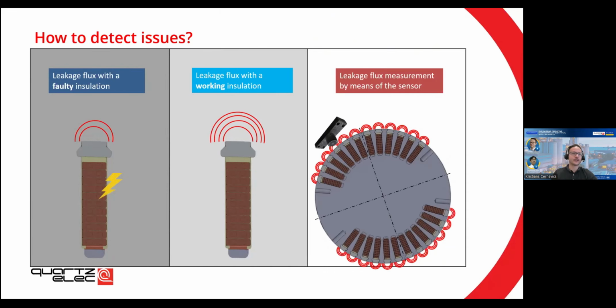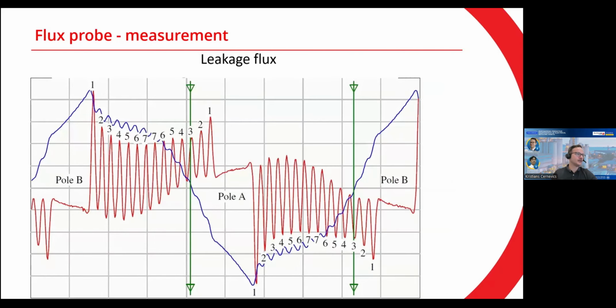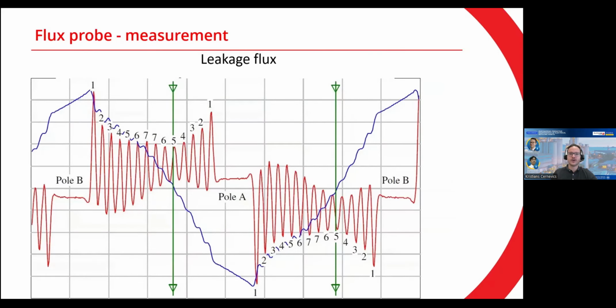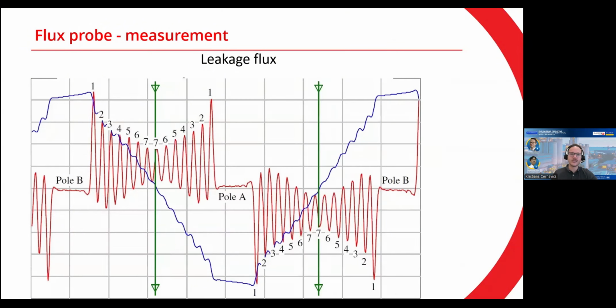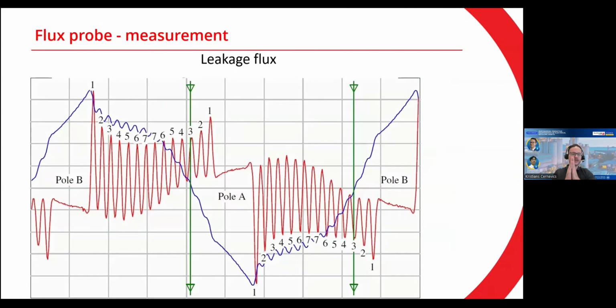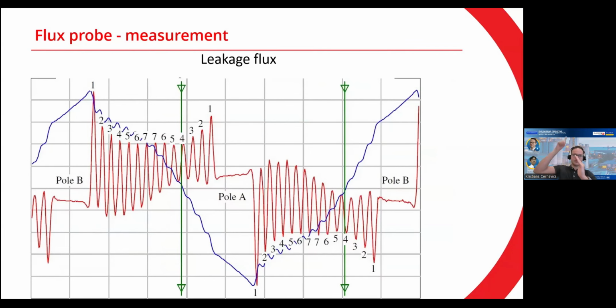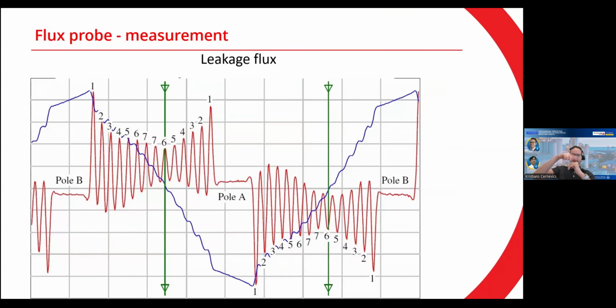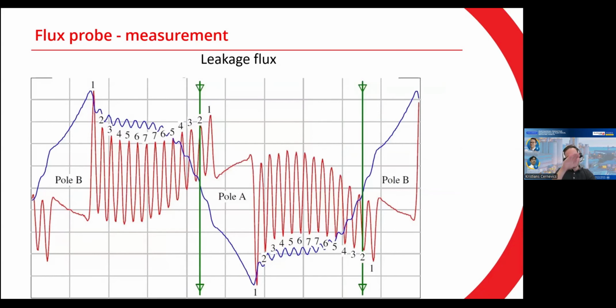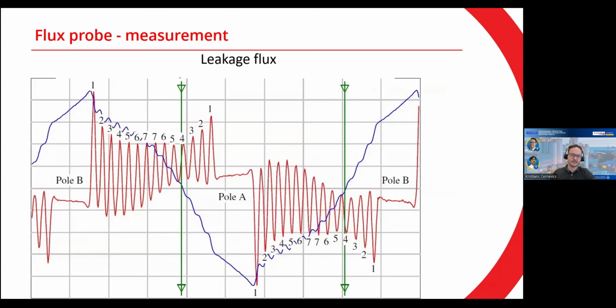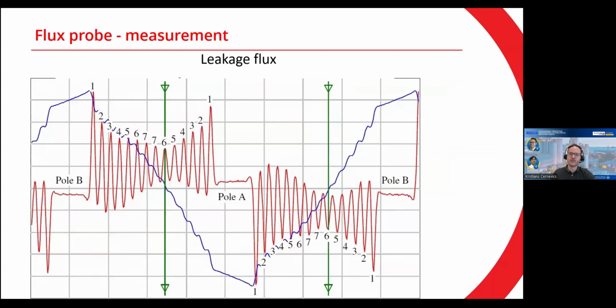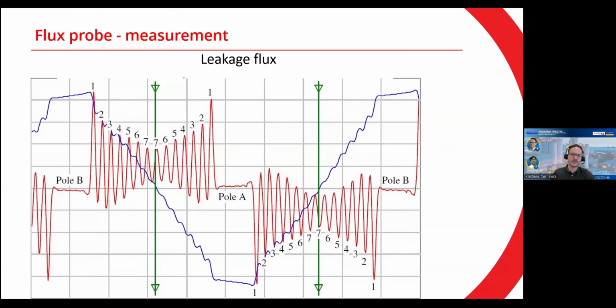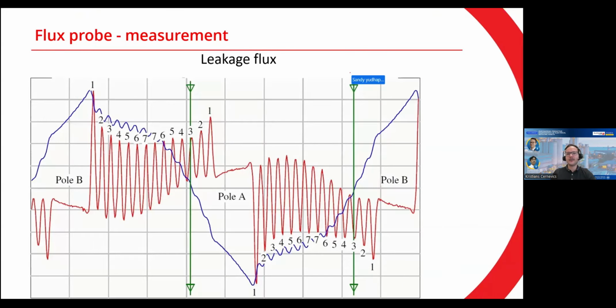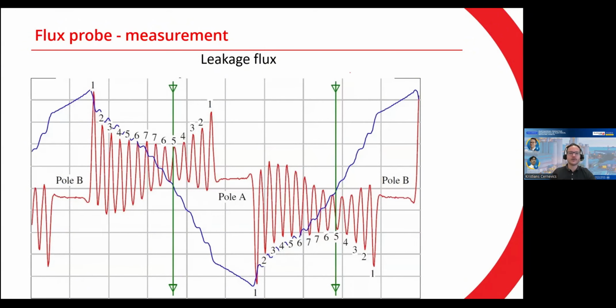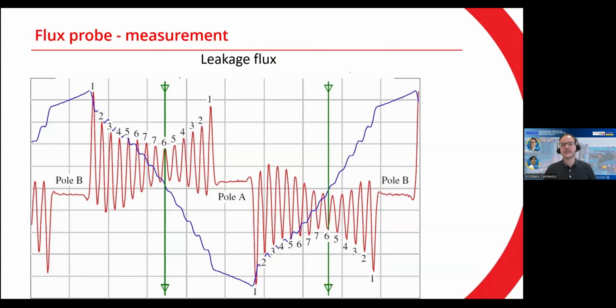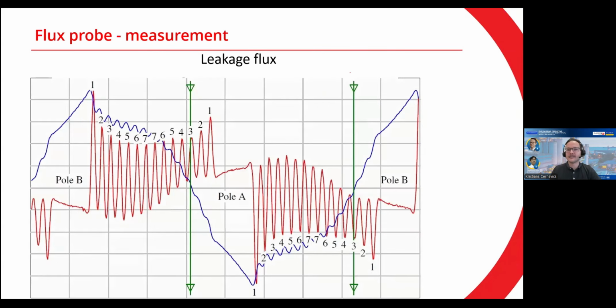Now if you look at this rotating right part and keep it in your mind, I'm going to show you how the actual measurement looks. So don't be scared here. The red part is the voltage measurement. Each of the coils has a particular peak. Once the sensor goes past the coil, there's a peak. Once it goes past the next one, there's another peak. Once it reaches the pole, there's going to be a bit of a flat line. And the blue part is the flux, which is just an integral of the voltage. And the green part, I'm going to explain a bit later on. This is essentially which of the coils is uncovered or more sensitive to this measurement.